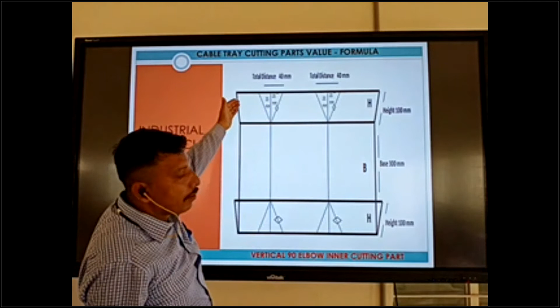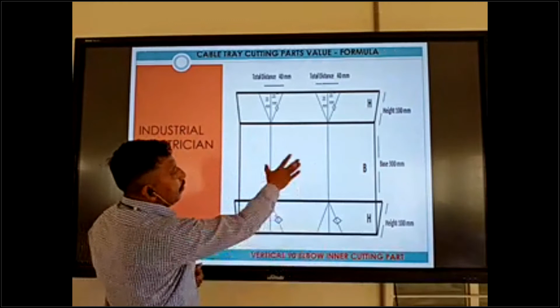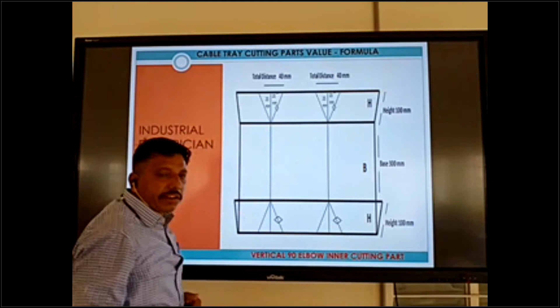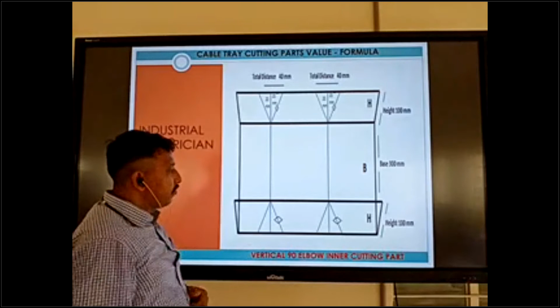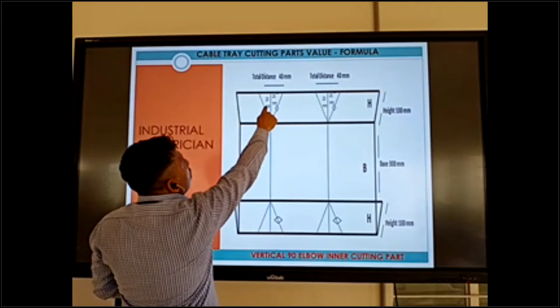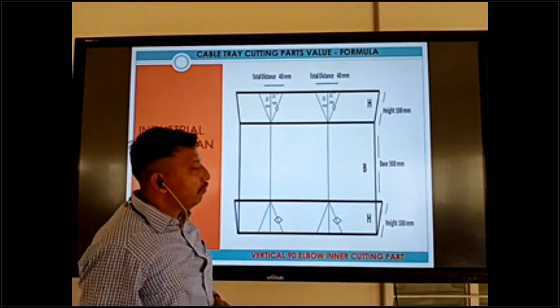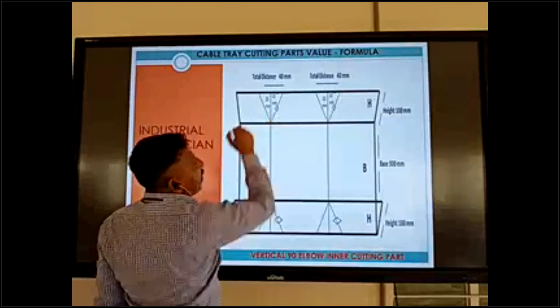100 mm, 100 mm, this is the height, and base is 300 mm. Now we are making the vertical 90, that time we don't care about the base, we only care about height. So the cutting part comes only on the height side for vertical 90. So this is the cutting part. Same as that, distance is, because this is 100 mm now, 100 mm multiplied by 0.4, so coming to 40 mm.